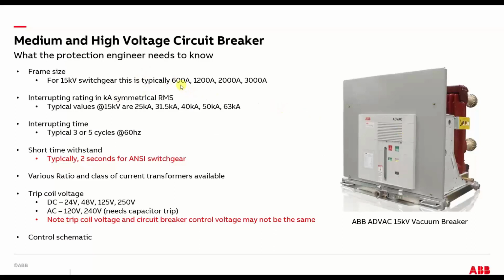A pretty typical frame size is 600 to 3000 for 15 kV class gear. That's it. So if you needed a 100 amp breaker for a 100 amp application, the smallest you can get is a 600. And actually, in medium voltage gear, we bottom them out at 1200. So if it's a 100 or a 200 amp breaker, you're in a 1200 amp frame. And all the actual trip setting is set by the CT and the relay.